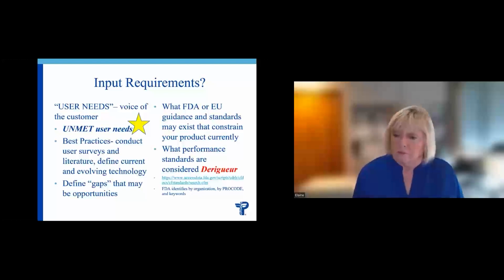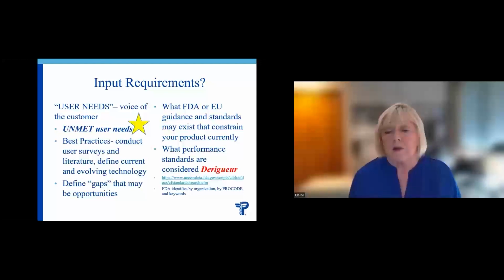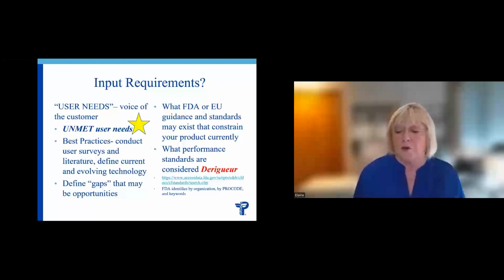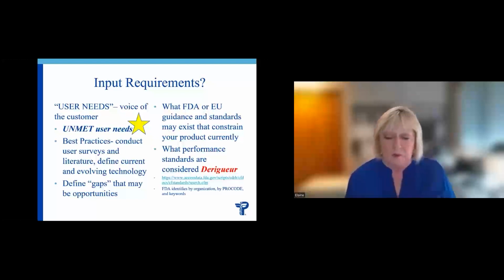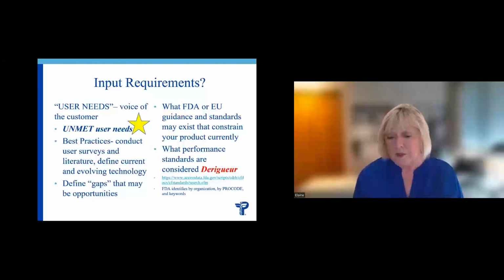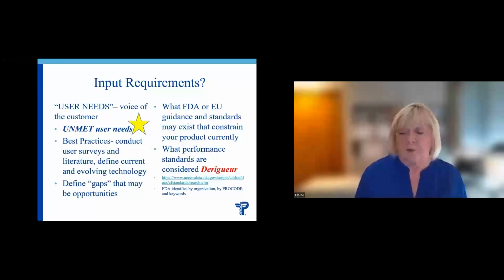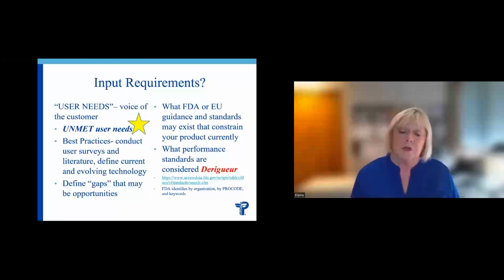Also, what FDA or, in fact, European standards and guidances may exist that constrain that product currently. Those constitute input requirements as well, and they're more along the line of engineering requirements, such as electrical standards or biocompatibility standards. So if we say at a user need level that it has to be biocompatible, we may have standards that help us define that in engineering terms. Also, we need to understand what performance standards are considered de rigueur, in other words, minimum requirements that we would have to meet. One of the best ways to start to find that, once you think you have the classification product code of your product, you can even go to FDA's website and punch in that product code or even the product description keywords and identify what standards FDA recognizes about your product.